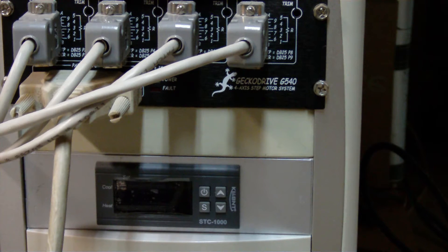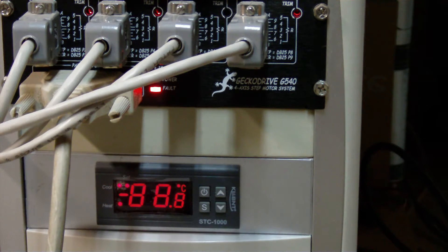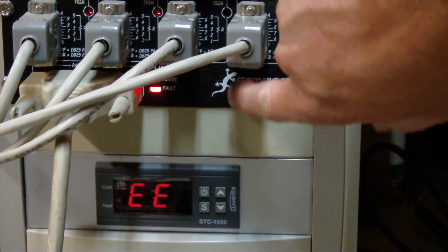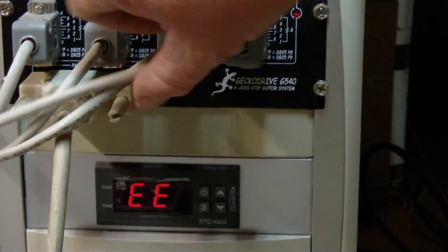So I'm going to turn it on to start with and I've removed the sensor. This simulates if the plug falls out. It's gone into an error state and you can see here that the fault light is on on the Gecko.